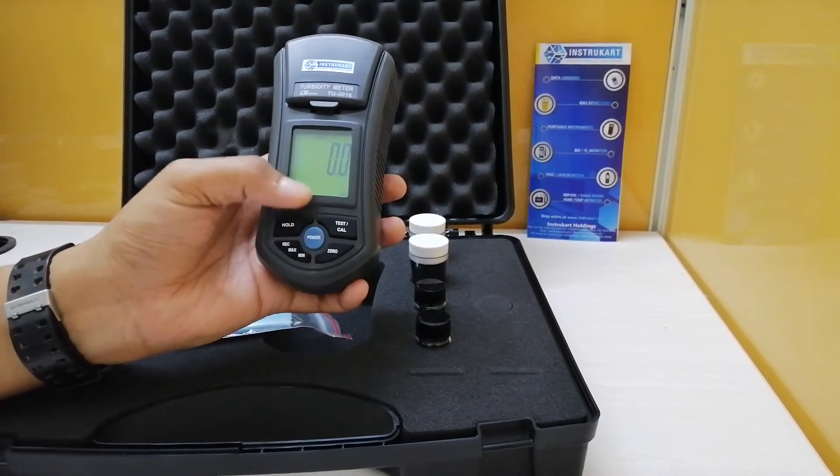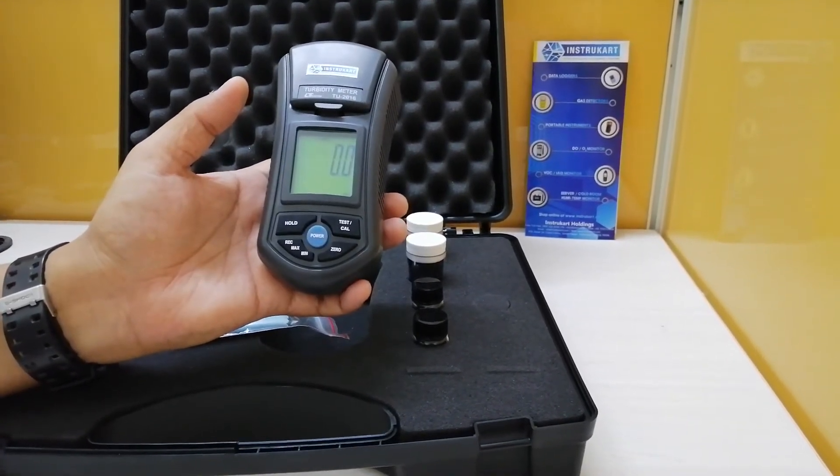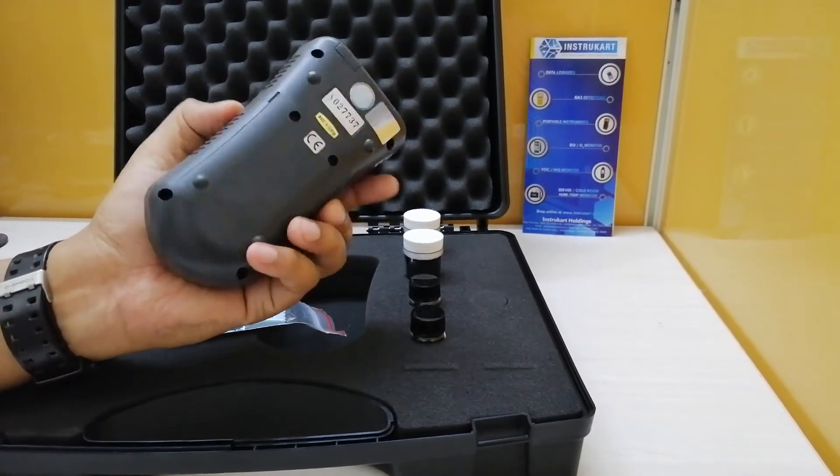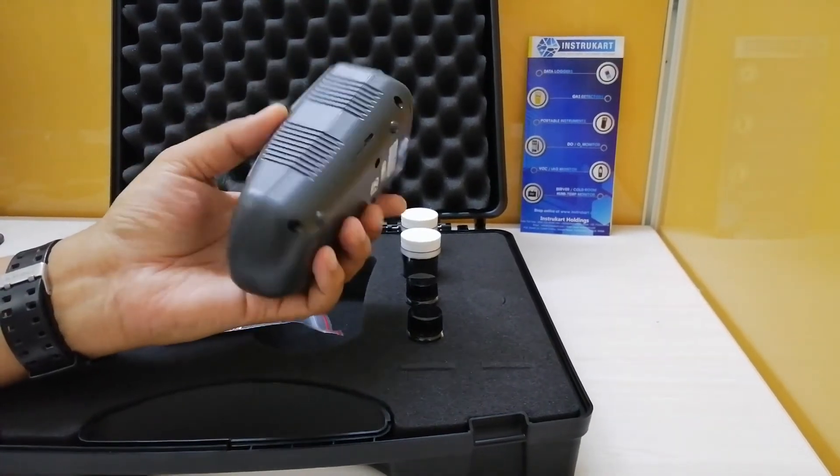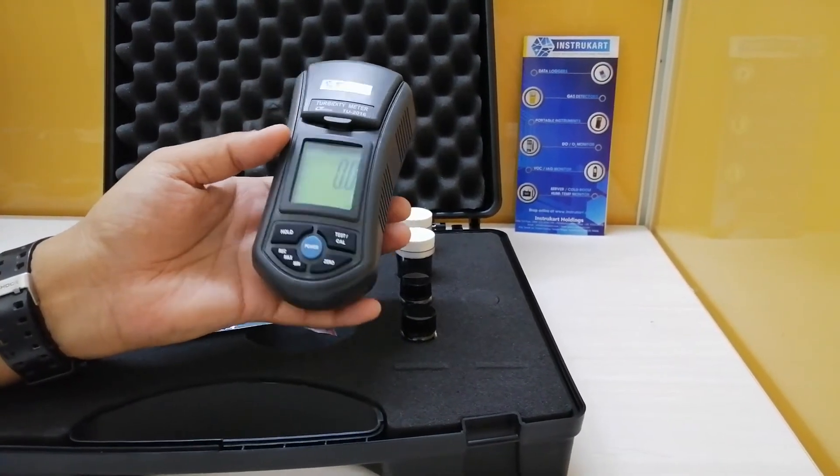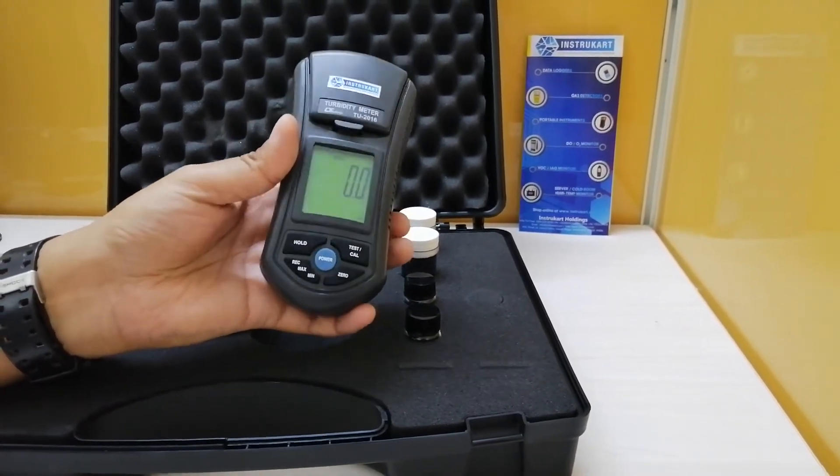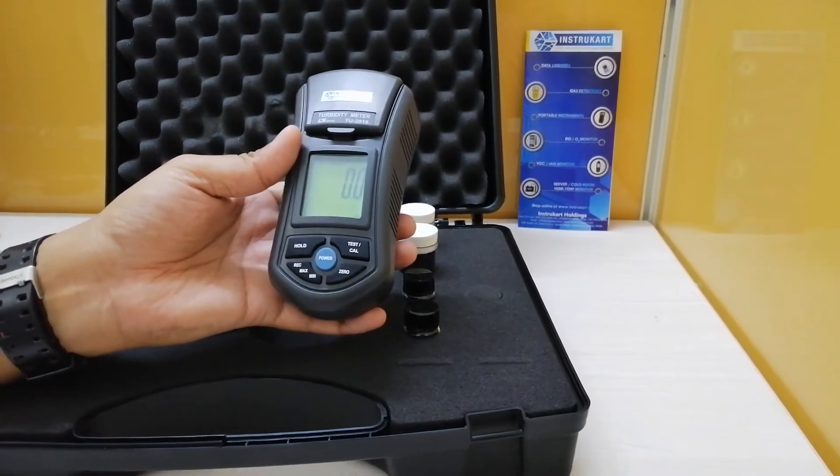It also has resolution settings. The ISO 7027 compliant design means it is very well suited for testing applications where you want to check the contamination of water with any suspended particles.